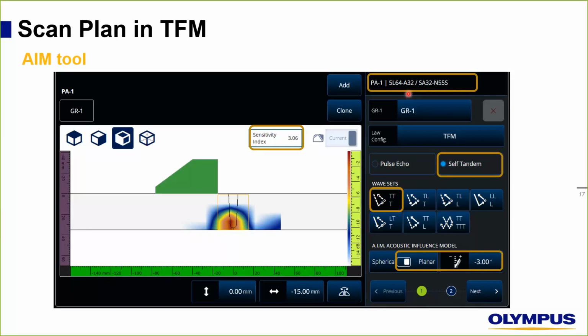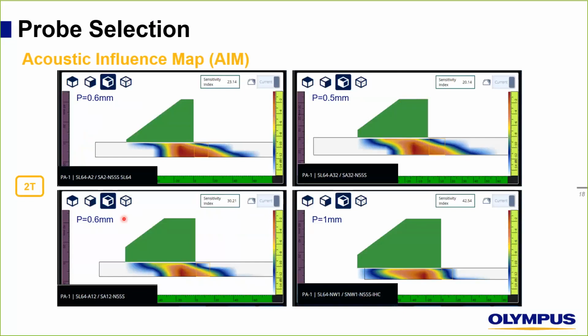This actually brings us to the next slide where we will compare 4 probes. Here we have 5L64A2, 5L64A32, 5L64A12, and 5L64 near wall 1. So we have the same number of elements and the same frequency. The only thing that changed here actually is the pitch, in addition, of course, to the wedge. And we can see clearly that for comparable pitch, we have the same coverage here in our zone. But when we change the pitch to 1 here for the near wall probe, we clearly see that most of the sensitivity, or the good coverage of sensitivity, is just below the probe and not inside our zone.